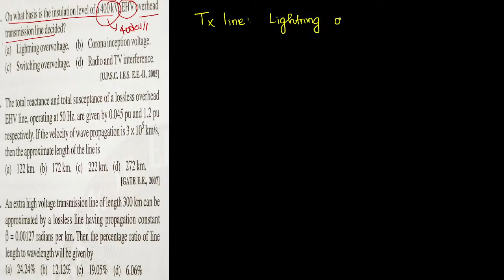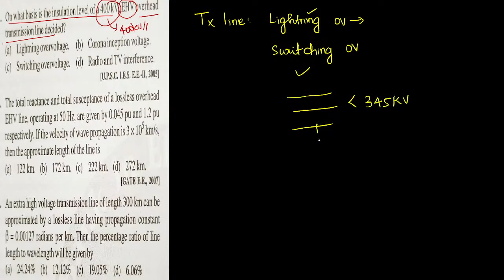So the insulation level of the transmission line will be decided based on the lightning over voltage and the switching over voltage. Lightning over voltage is given preference when your transmission line is carrying less than 345 kilovolt. In that transmission line, wherever you are giving insulation, the insulation rating will be decided based on lightning over voltage. Suppose the transmission line is carrying greater than 345 kilovolt, in that case insulation levels will be decided based on switching over voltage.